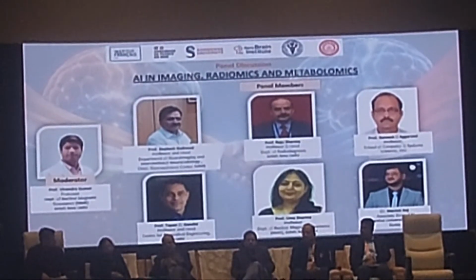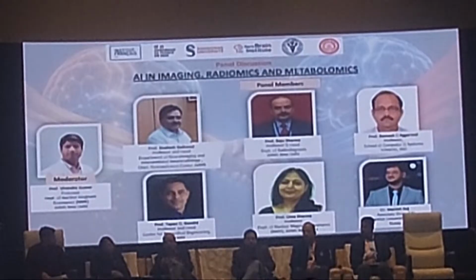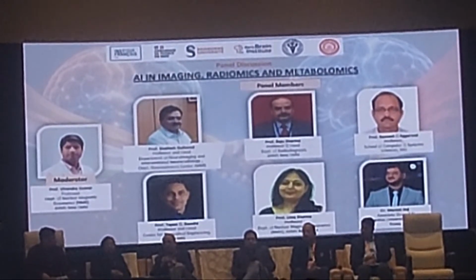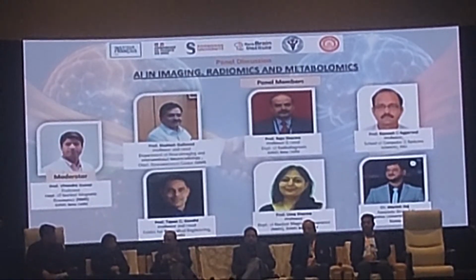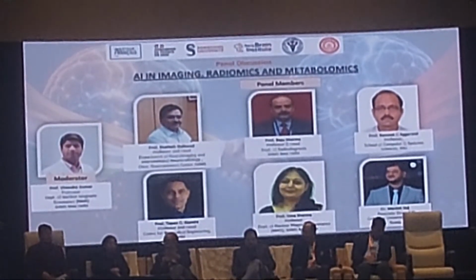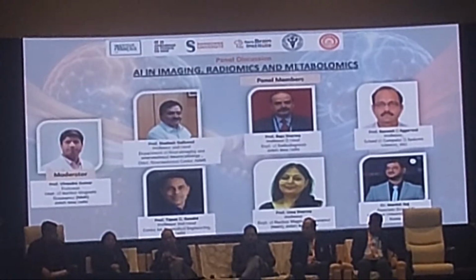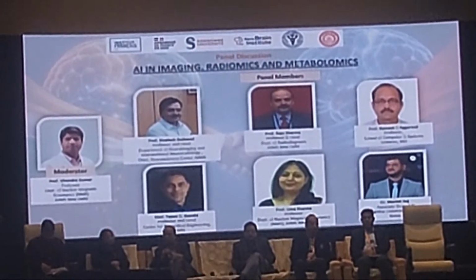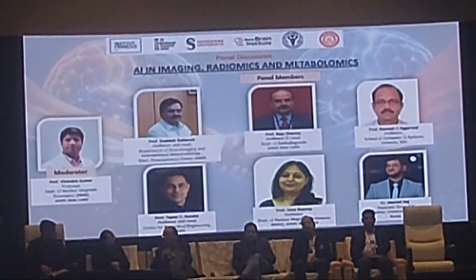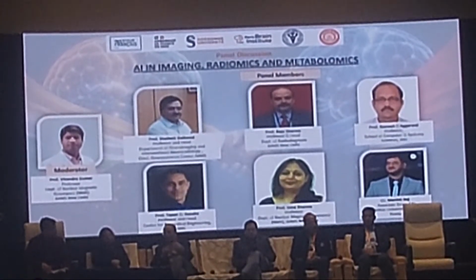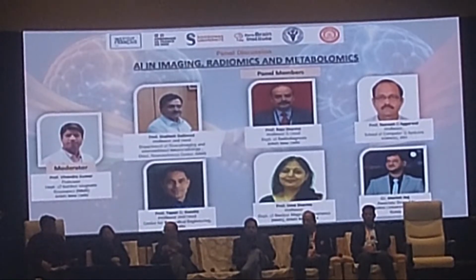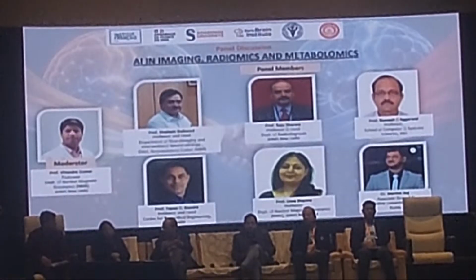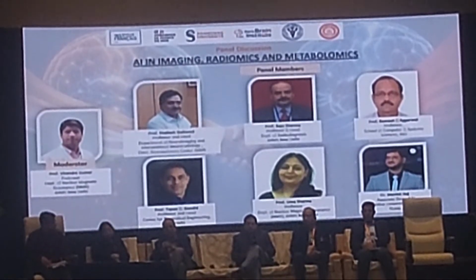The third interesting experiment that we have tried, similar to what Shailesh was talking about, in a project with the University of Michigan, we have put a low-field magnet in a rural area. We have put it in the Ballabgarh rural facility that AIIMS runs. We have a 0.55 Tesla magnet there, and that also uses a lot of AI algorithms to improve the image quality. So you can do what is called an accelerated MR with a very short protocol, and then improve the quality by using AI. There are multiple algorithms which improve image quality.